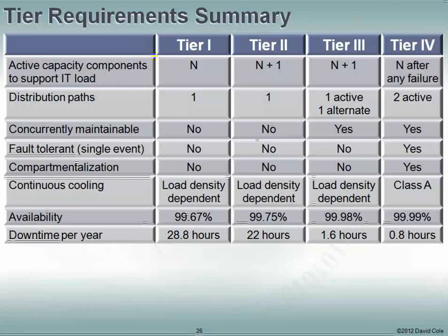Looking at distribution paths: Tier 1 and Tier 2 only have one. Tier 3 introduces this second distribution path. What's important about that is if you look at the next line, concurrently maintainable—it's no and no for Tier 1 and 2, but yes for Tier 3, because of that extra distribution path.